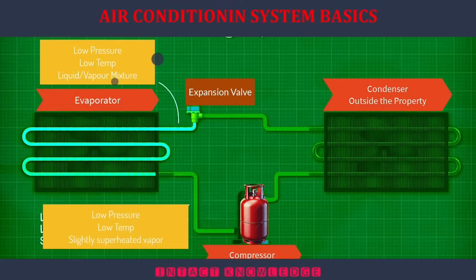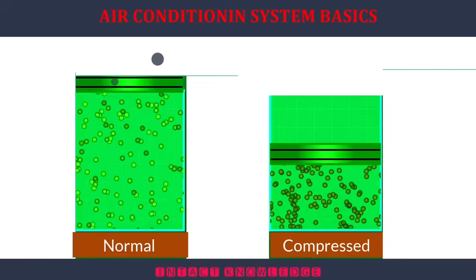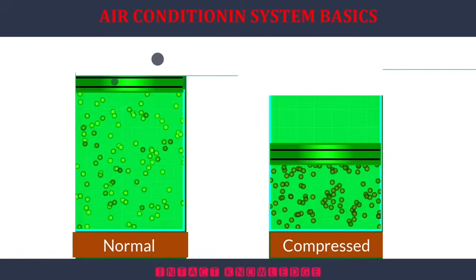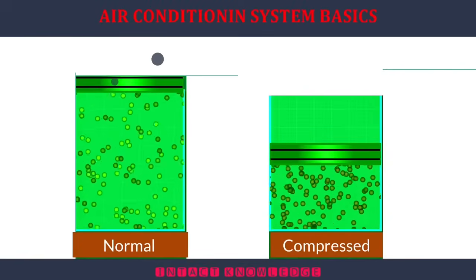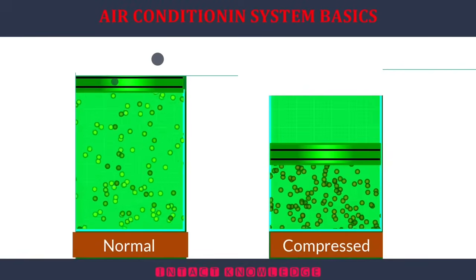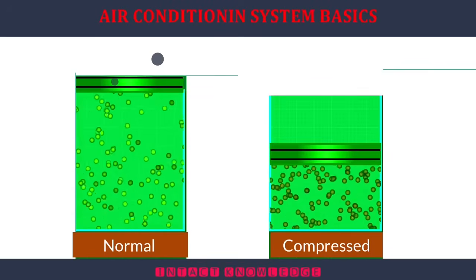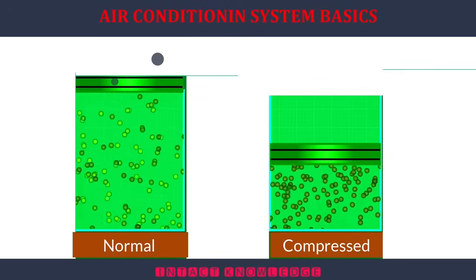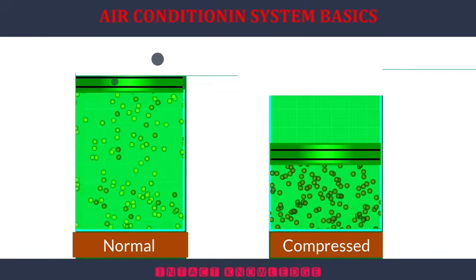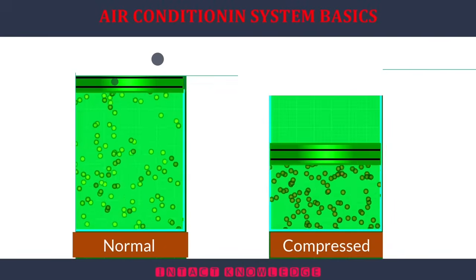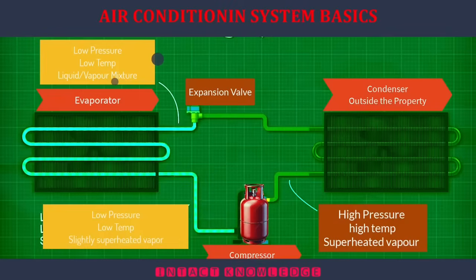It then squeezes this together into a much smaller space, and so the pressure increases. All the heat which was picked up in the evaporator is now contained in a much smaller volume, so the temperature will increase. This is very important, and we will see why in just a moment. But if you've ever pumped up a bicycle tire, you will notice the pump becomes hotter as it's compressing the air. The refrigerant is then pushed into the condenser, where it enters as a high-pressure, high-temperature, superheated vapor.